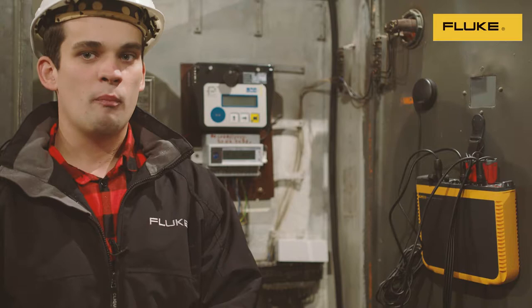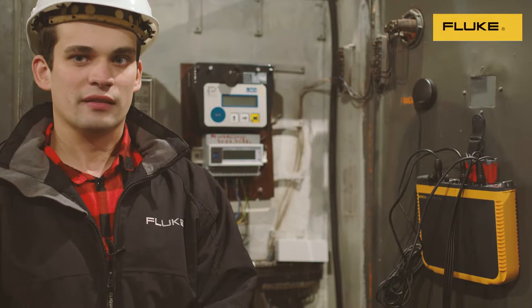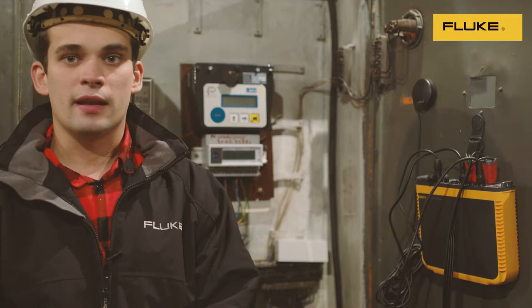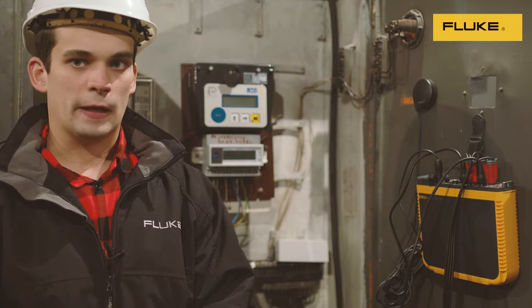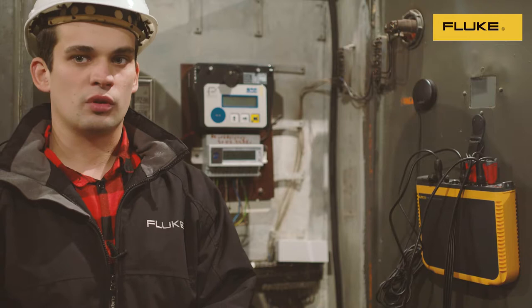A special group of power quality measurements are those done on secondary windings of current and voltage transformers. In this case, we're dealing with secondary windings of current and voltage transformers installed on a medium voltage line. In such applications, it's not recommended to use Rogowski coils.